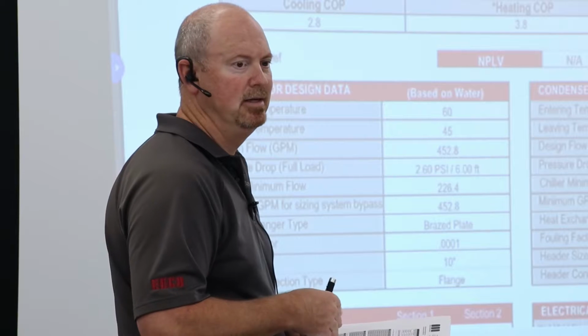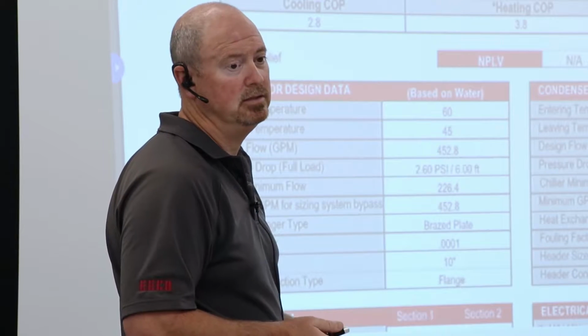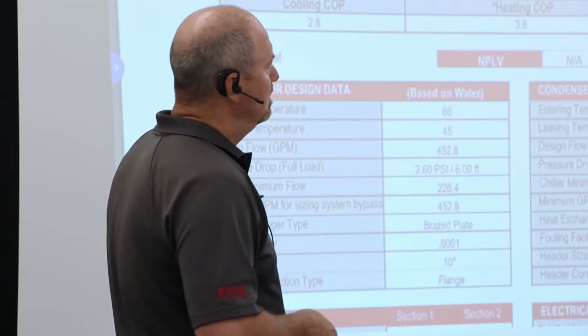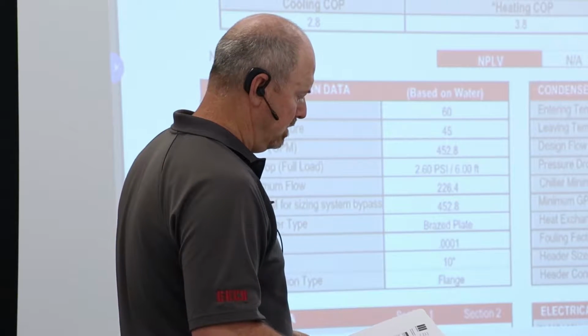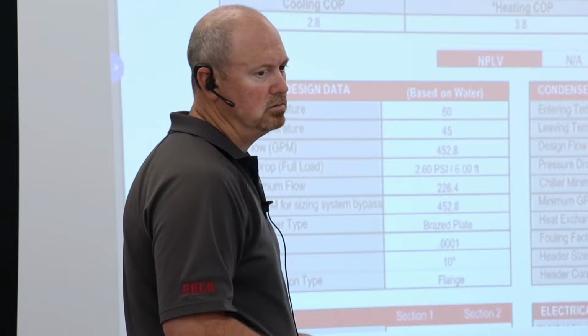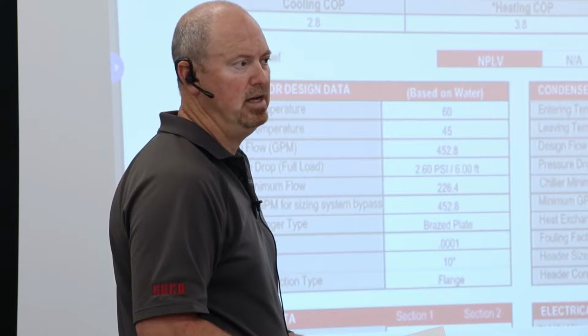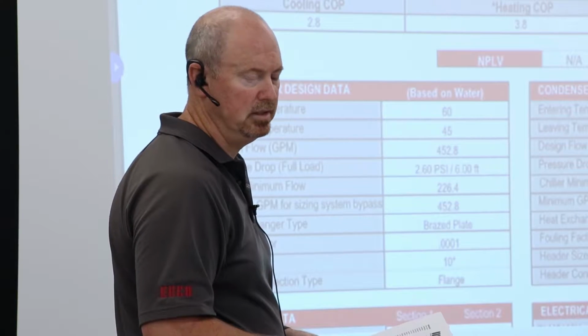So chilled water flow alarms and stuff like that would have something to do with pumps in the facility. That's going to be an issue until bugs get worked out with the controls usually. If it does that, it's really not the chiller, it's more of a flow to the chiller. It pretty much does its own thing. I lean on that a lot because it happens a lot. A lot of the other stuff I need to go over, you'd be better off, more beneficial at the chiller, going through the program and letting you know.